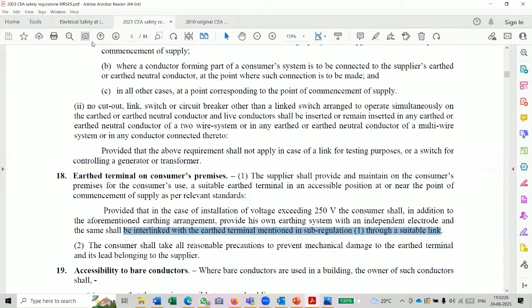This is tending towards a common wording, that is MET. That MET is to be followed, then the earth terminal should be provided by the supplier. This is the norm. But unfortunately, when the consumer tries to connect his earthing terminal with the supplier's earthing terminal, all the problems will occur. The temporary overvoltage. These temporary overvoltages shall definitely occur because the suppliers themselves are adopting various measures throughout this country.